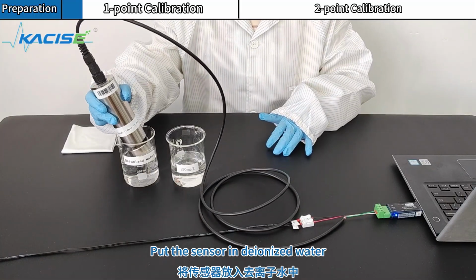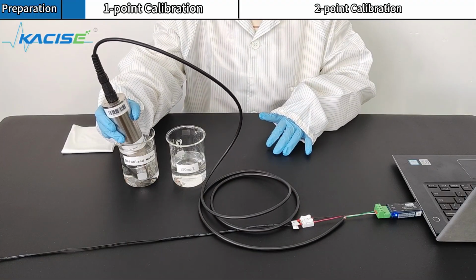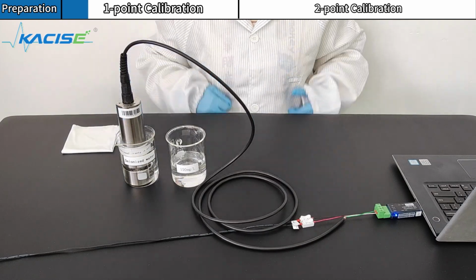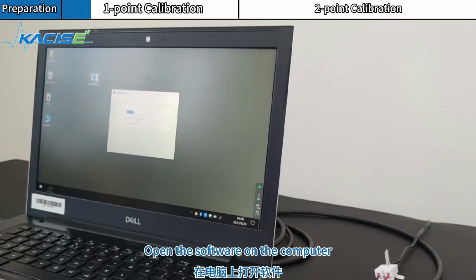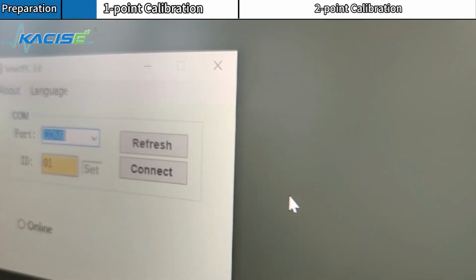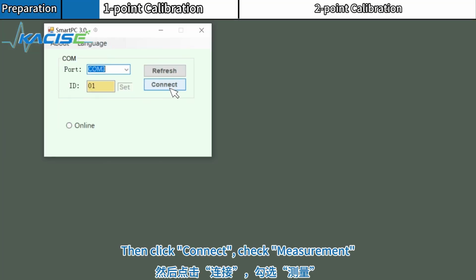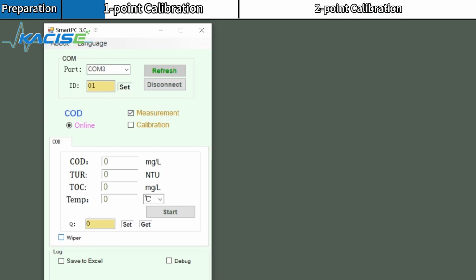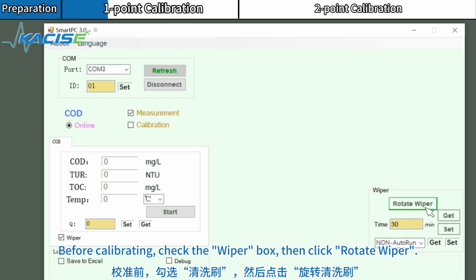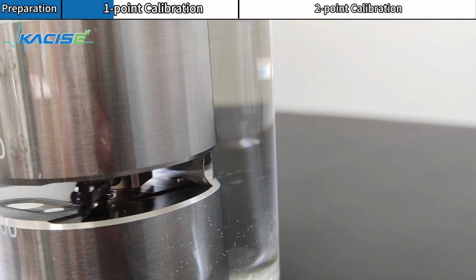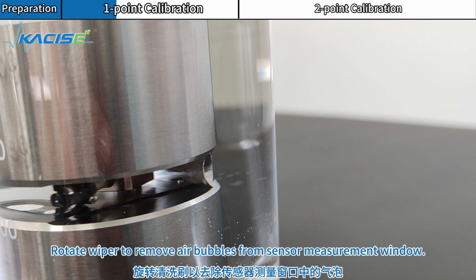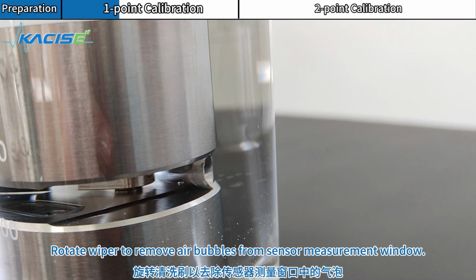Put the sensor in deionized water. Open the software on the computer. Then click Connect, check Measurement. Before calibrating, check the wiper box, then click Rotate Wiper. Rotate wiper to remove air bubbles from sensor measurement window.